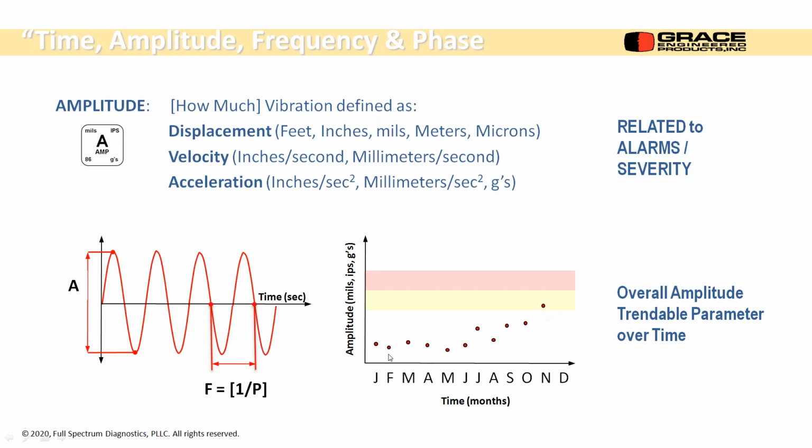So that's the greatest thing about doing these transducers to stay in one place all the time, and they're constantly taking data. There's no human interaction to bother them. They get fantastic trends. This would be like January, February, March, April, all that for route-based measurements. You get 12 measurements a year. If I took a measurement every day, I'd get 365 measurements with the in-place wireless transducers.